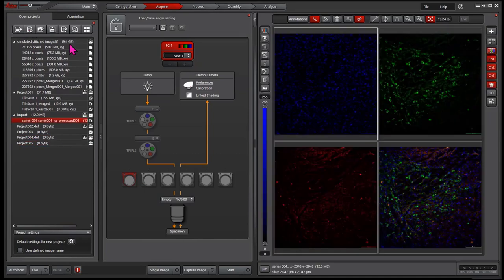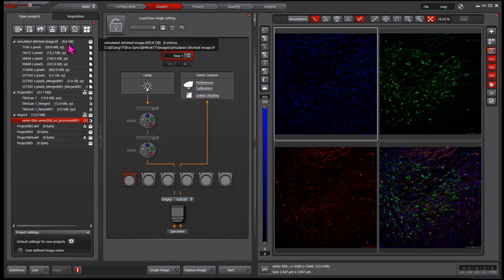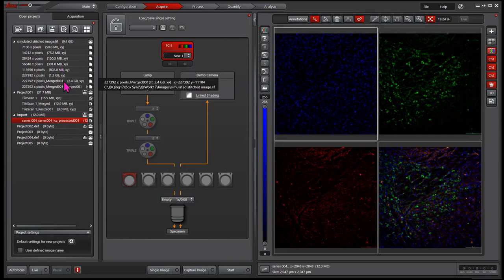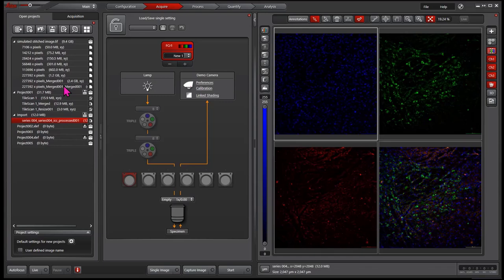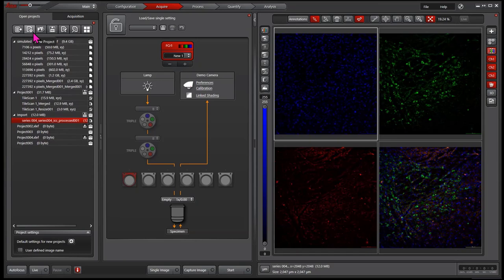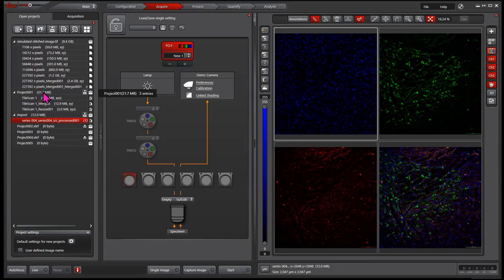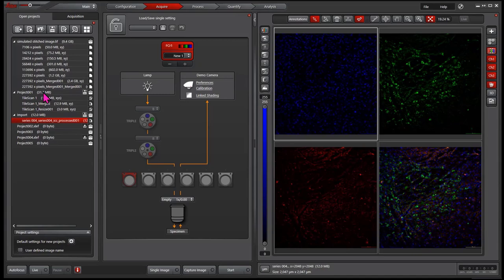How does the LIF file get too big? One reason is LIF file format is just a container to store all the images. It can hold many image series for the same experiment. So when a lot of pictures are stored in one file, the size will get big, of course. So my suggestion is create a new project whenever you switch a slide or sample, or keep monitoring the size so that the size is smaller than 4 gigabytes. So it's easy to copy by USB or upload through cloud.